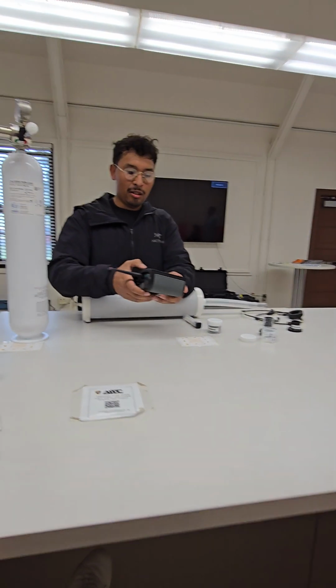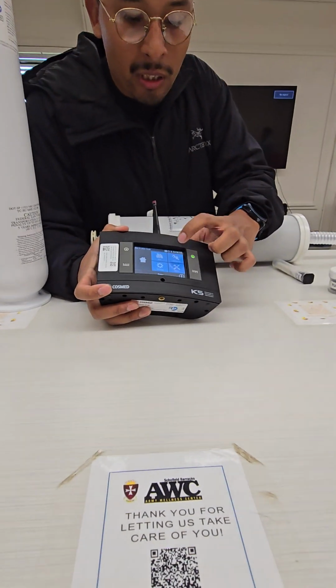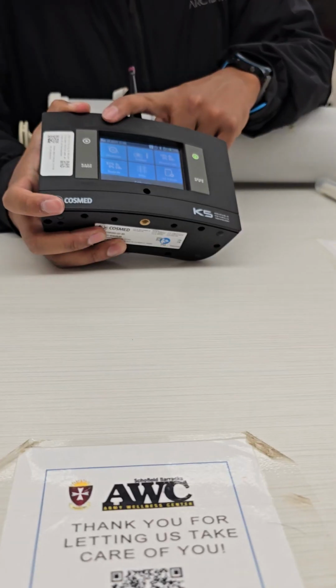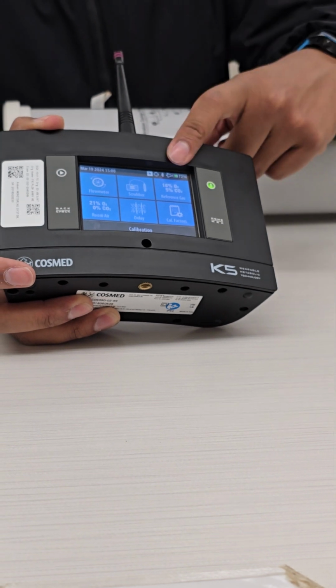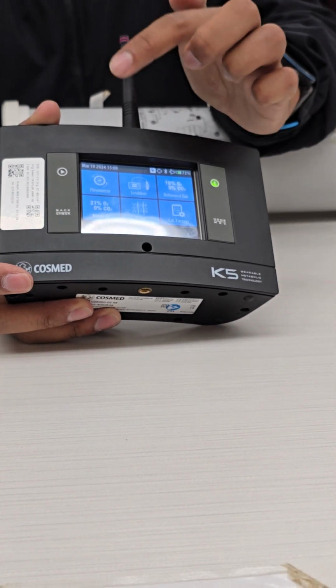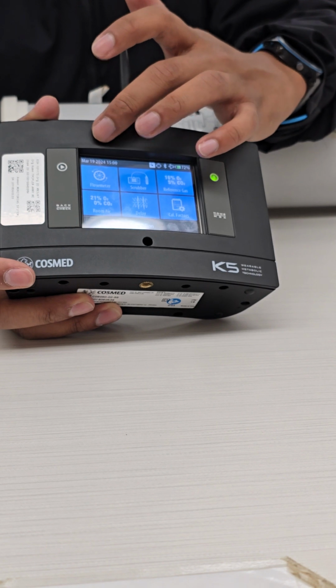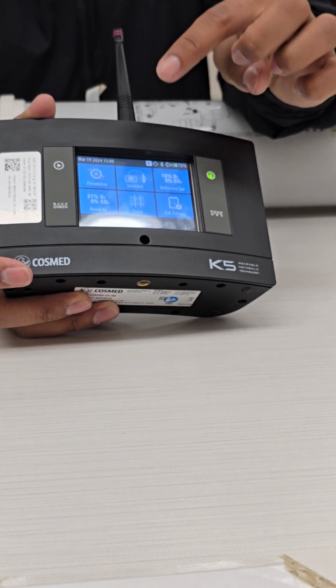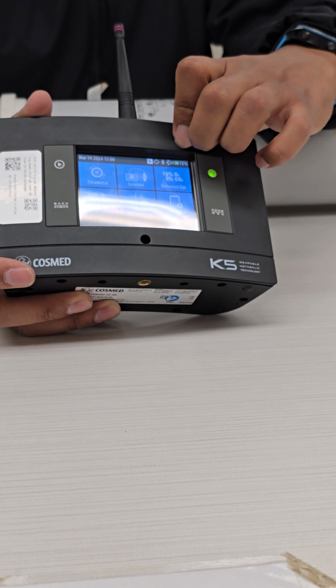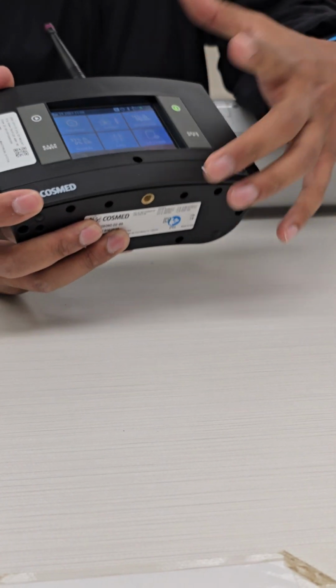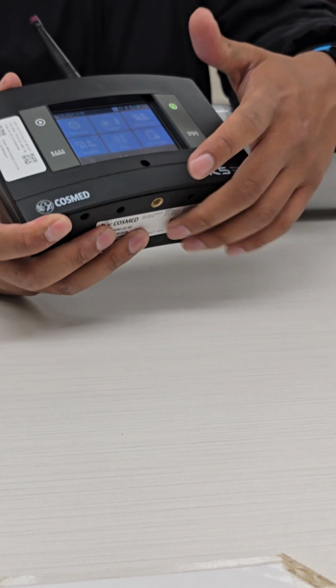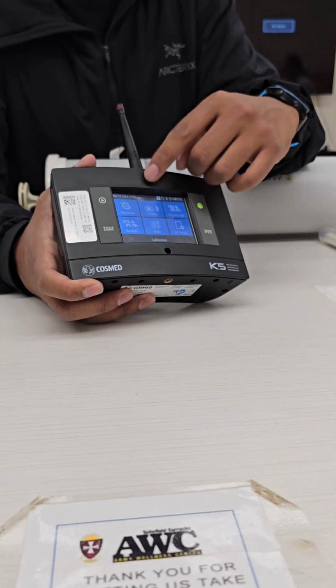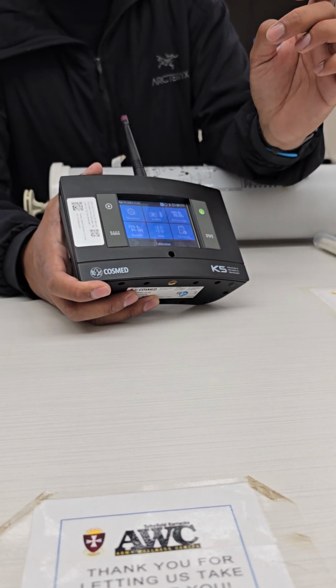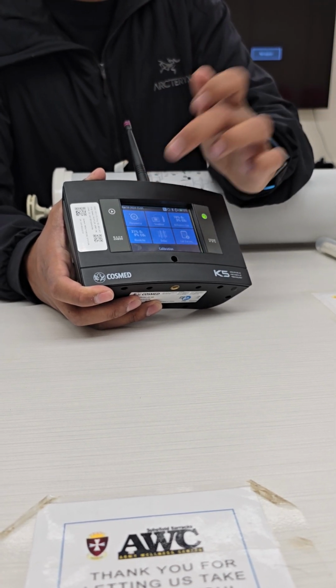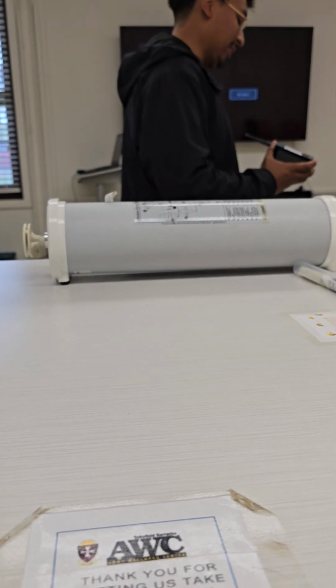Start with a flow meter, and let me actually show you real quick. I'm going to go into the calibration side, and I usually just go left to right. So it starts with flow meter, then it goes to scrubber, and then you do reference gas. Technically, the flow meter can be completed whenever, but you have to do the scrubber before you do the reference gas. So what's happening is you want to zero the analyzer of CO2 before you go into the reference gas. So make sure you do the scrubber before this guy. But we're going to start with the flow meter, and I'll show them actually.